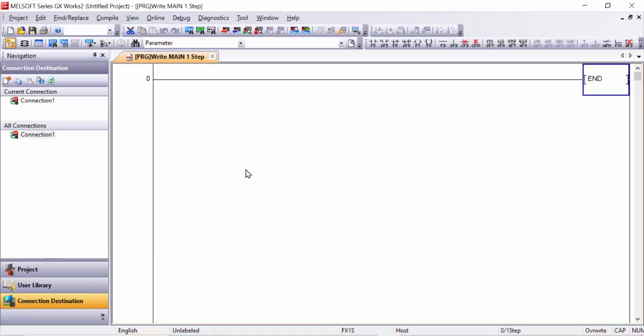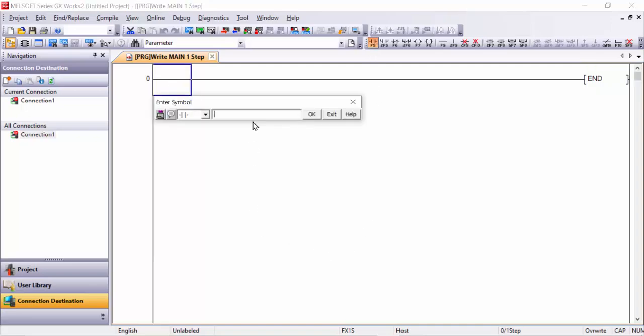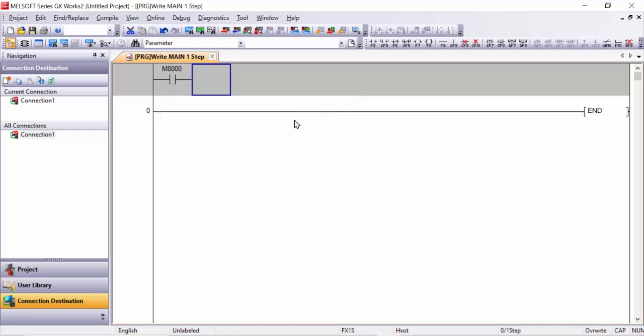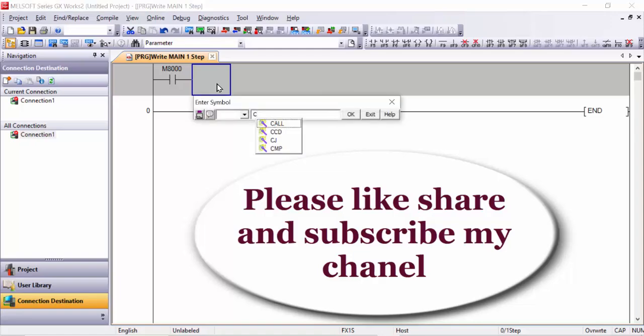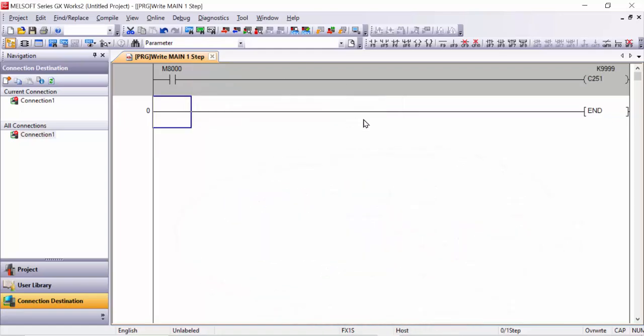First of all, we will open our GX Works 2 software and here we will take one internal memory M8000 and click OK. Then next we will take one counter C251 and a value which you like to give, for example K9999. I will give this one and click OK.